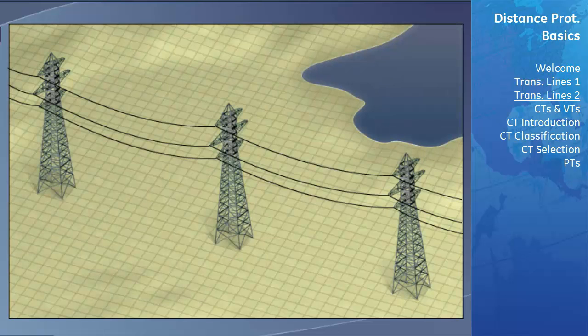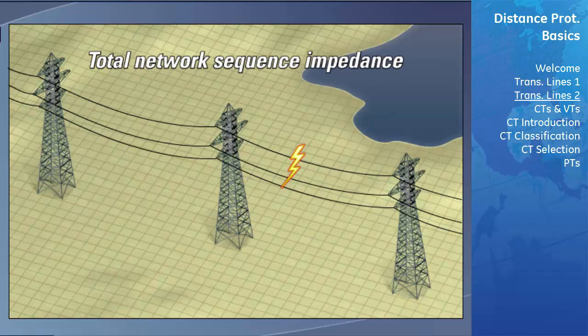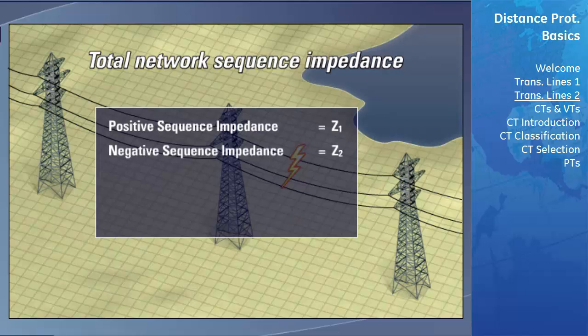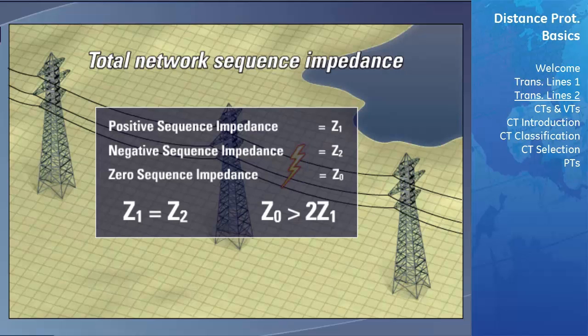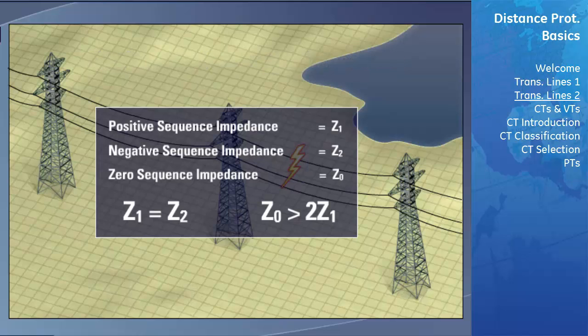In order to calculate sequence currents and voltages correctly during faults, the total network sequence impedance of the transmission line system needs to be calculated using the positive sequence impedance, negative sequence impedance, and zero sequence impedance. For transmission lines, under most circumstances, the positive sequence impedance is equal to the negative sequence impedance, and the zero sequence impedance is usually greater than two times the positive sequence impedance. However, these values can change depending on the grounding path and the geography of the line.